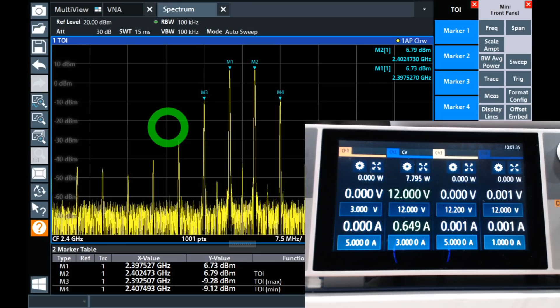But I also want to know what is actually the total power leaving the device right now. Now, one of the things about multiple tones is that if you want to know the total power, you're going to have to measure and calculate and add them all up, even though most of them are quite different from each other. If you have multiple tones of the same value, you need a power sensor that accumulates all the power and integrates them for you. Now, as I showed you earlier, I already have a power sensor connected to this instrument, so why don't we go ahead and configure it.